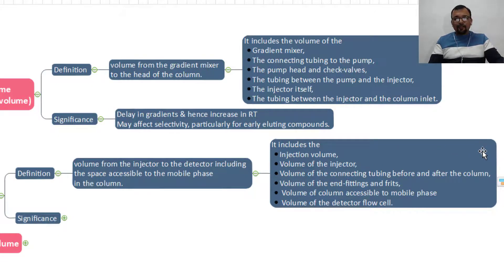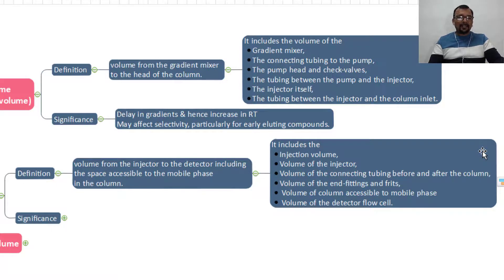The components that account for the void volume are: injection volume, volume of the injector, volume of the connecting tubing before and after the column, volume of the end fittings and frits, volume of the column accessible to the mobile phase, and volume of the detector's flow cell.